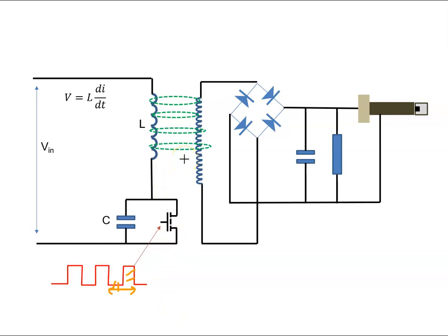That's the basic principle of an ignition system. Whether this is for a car or for a gas turbine, the basic principle is the same. In a car, this used to be the points. In a piston engine aircraft they still use points in the magneto, but in cars they replace that with the transistor and this is called electronic ignition. That's how we get this very large voltage on the igniters.